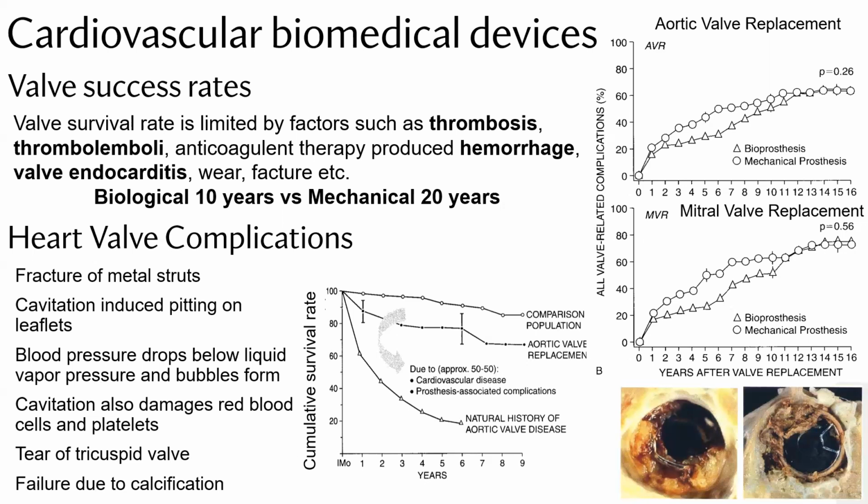But really, in terms of the heart valve itself, you can have fracture, you can have fatigue, just like any other mechanical component. But one that's really highlighted here is cavitation, because sometimes the blood pressure drop actually, vapor evaporation basically happens either under increased temperatures or reduced pressures, meaning that you reach the vapor pressure.